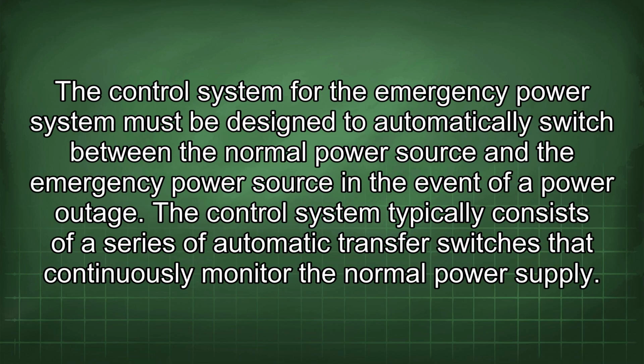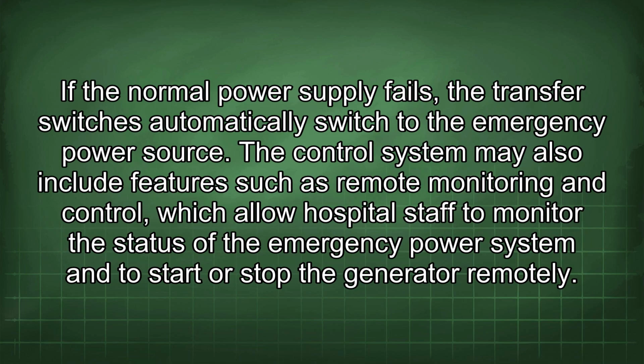The control system for the emergency power system must be designed to automatically switch between the normal power source and the emergency power source in the event of a power outage. The control system typically consists of a series of automatic transfer switches that continuously monitor the normal power supply. If the normal power supply fails, the transfer switches automatically switch to the emergency power source. The control system may also include features such as remote monitoring and control, which allow hospital staff to monitor the status of the emergency power system and to start or stop the generator remotely.